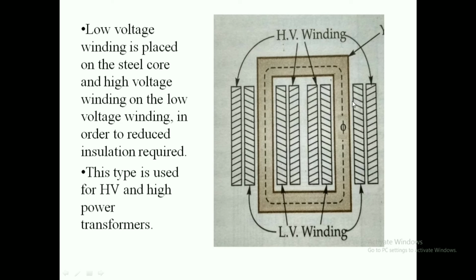In the next leg also, in the same way, 50% of the low voltage winding is placed over the magnetic core and 50% of the high voltage winding is placed over the low voltage winding. This type of arrangement is used just to reduce the insulation required. And this type of core type transformer is generally used for high voltage, high power transformers.